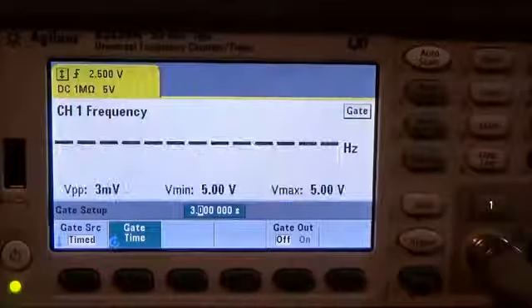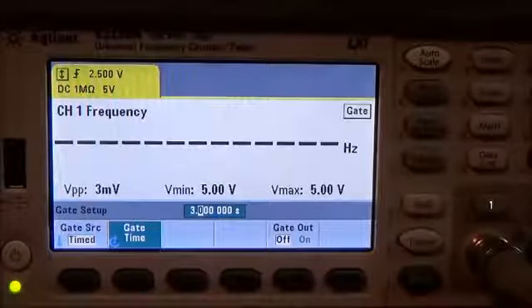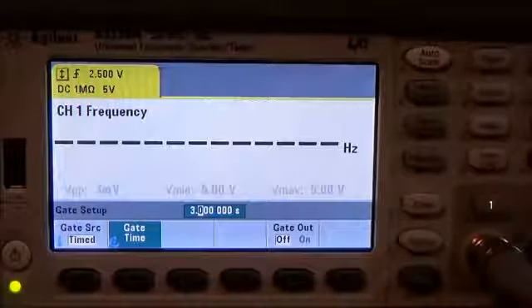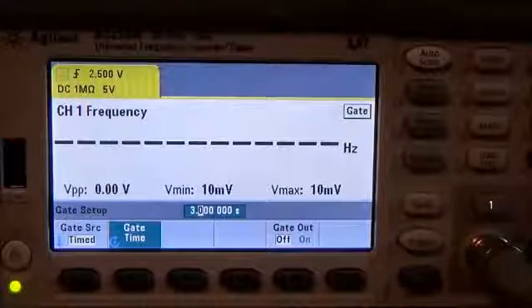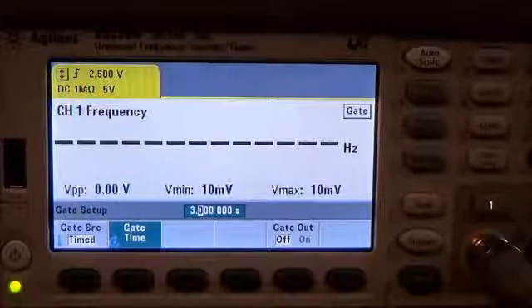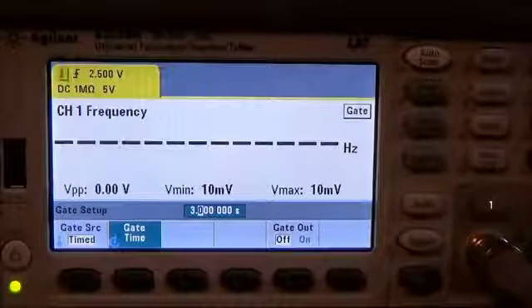Finally, the last hint and probably the most important one is to check the measurement timeout. A new feature with these 53200 series counters is the ability to actually set the amount of time you would allot for a measurement to be made.